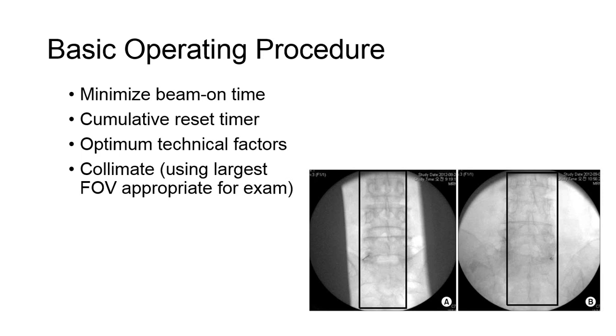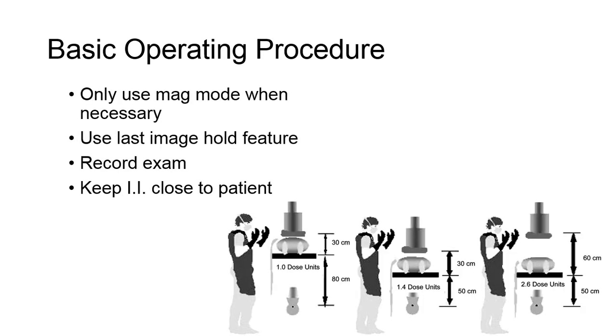Many forget to include collimation during fluoro. Limiting the beam size with the shutters visible on the TV monitor, along with selecting the largest field of view appropriate for the examination, will dramatically reduce patient dose. Magnification mode uses more radiation than the largest FOV possible, so limiting its usage to only when absolutely necessary will reduce radiation exposure.